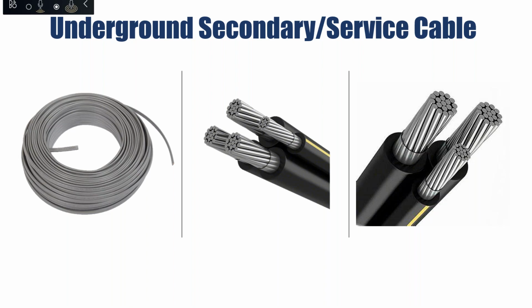In the middle and right sections, you can see one cable has a yellowish green stripe on it. That's the neutral grounding cable we use, and we strive to ground our system very well. That serves as the ground or neutral for the system that goes to your home or business. The other two are hot legs, and generally you'll have 120 on each leg, and 240 between those.